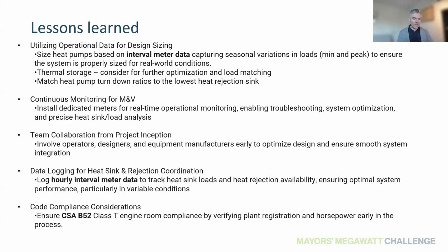Again, like you guys said, the metering data is pretty critical to understand when your refrigeration plant is running. If you don't have supervisory control — for example, if you have a big load calling and your ice plant isn't — you could look at overcooling your ice surface by a degree or two so you can satisfy those heat loads using heat recovery. So if you're not well integrated from a controls perspective, having that thermal storage is key.